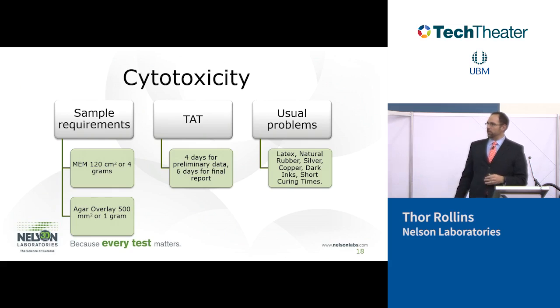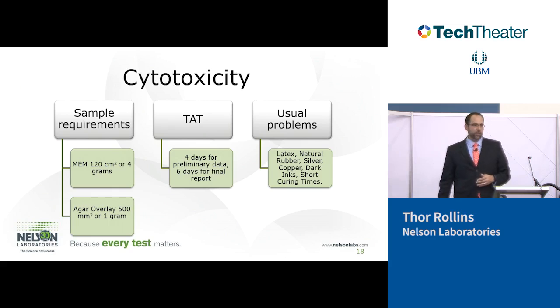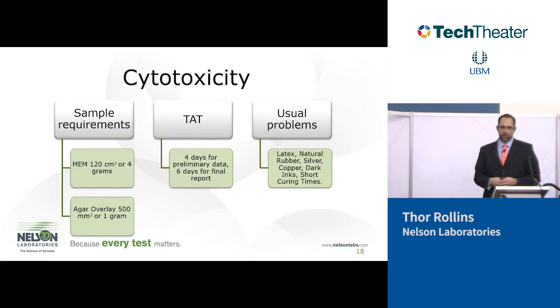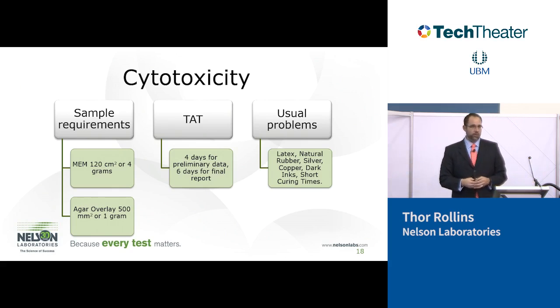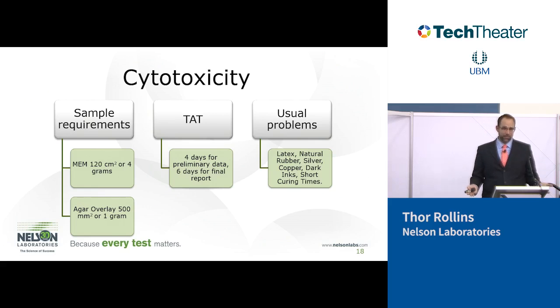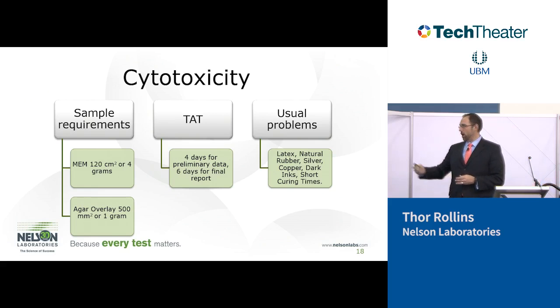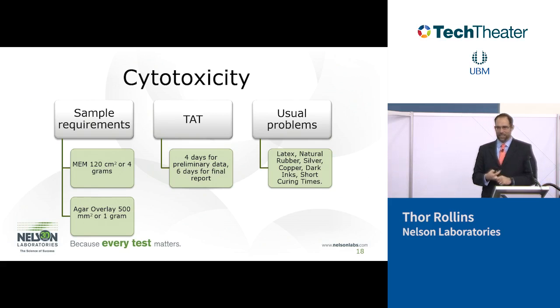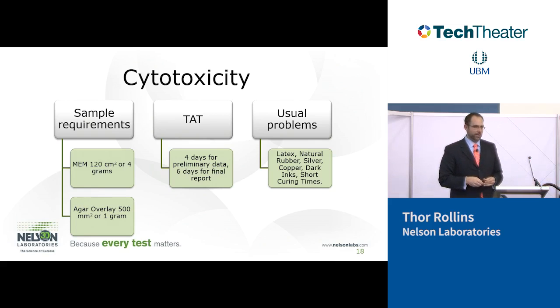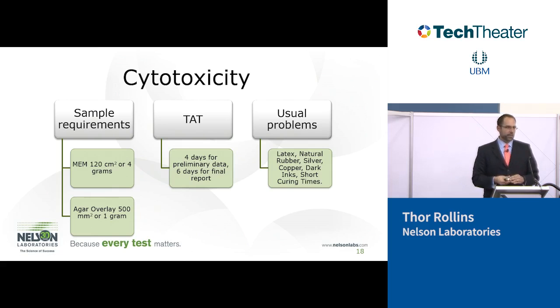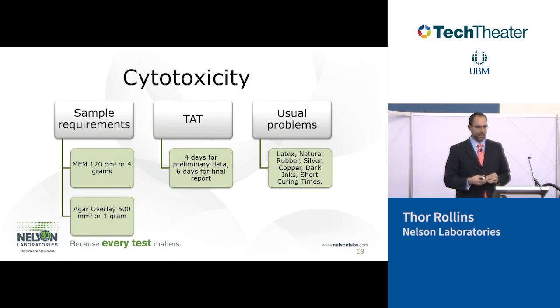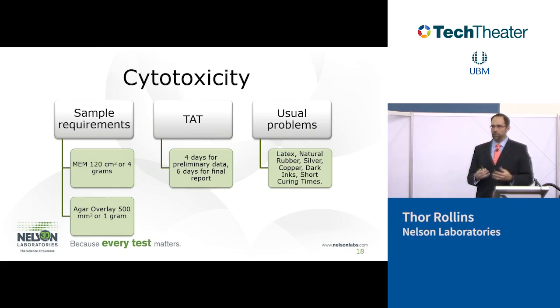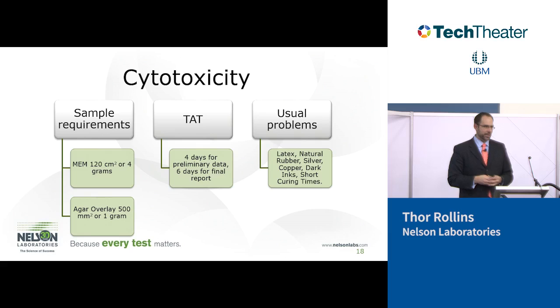But it gives you an idea of turnaround time, sample requirements for cytotox, and some of the problems we usually see with cytotoxicity. Latex is our positive control. So if you have latex in your device, you're going to probably fail cytotox. We most likely see problems with silver, copper, zinc. Those metals are all cytotoxic. It just happens that some of the dark colors of inks, like blues and blacks, have a lot of copper and zinc in them. So if inks leach off the device, they'll also cause cytotoxicity.